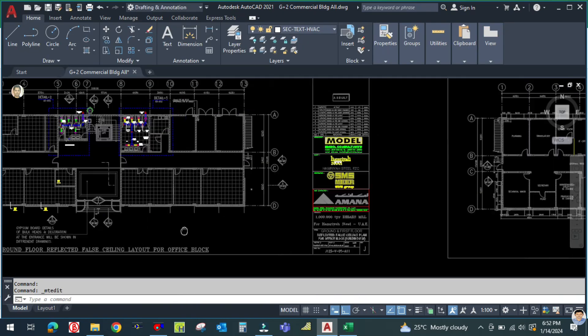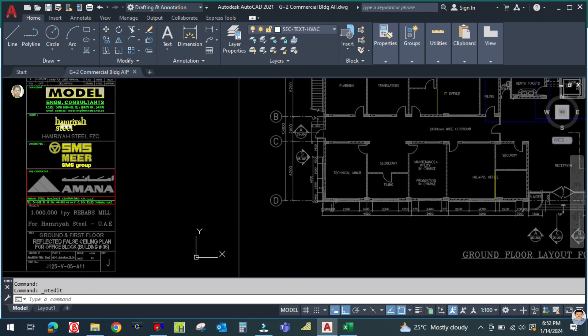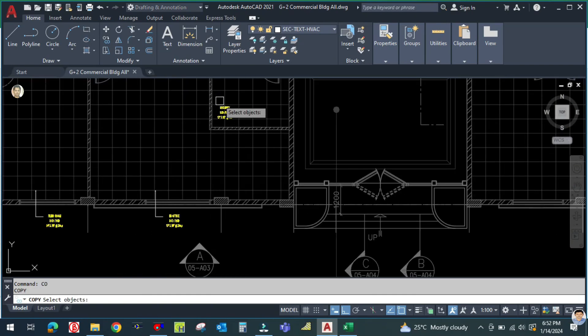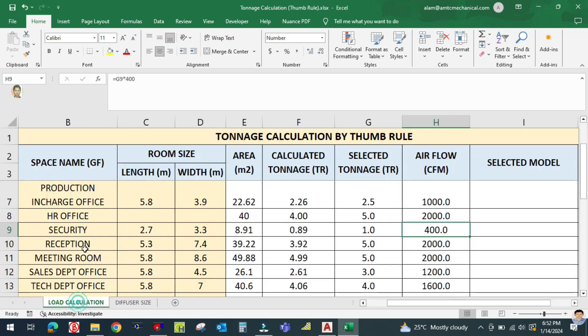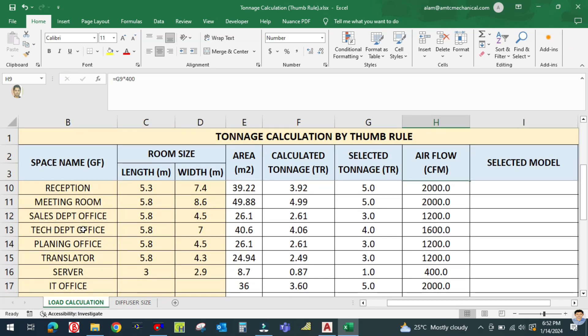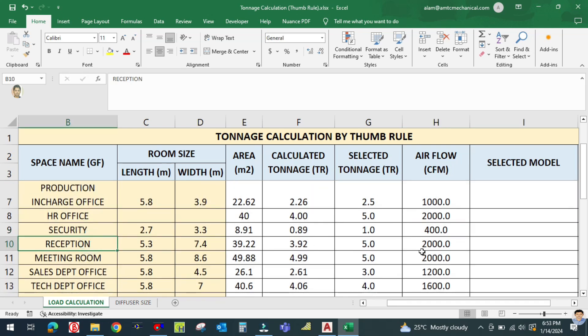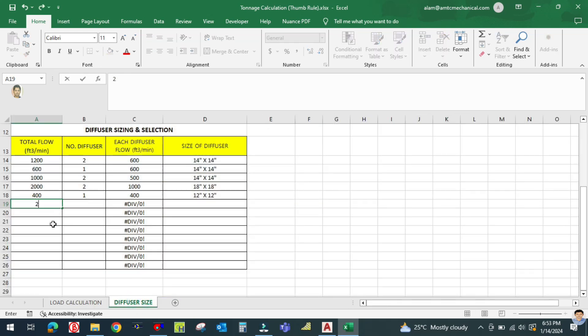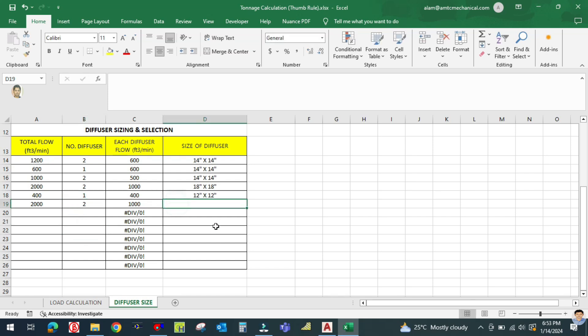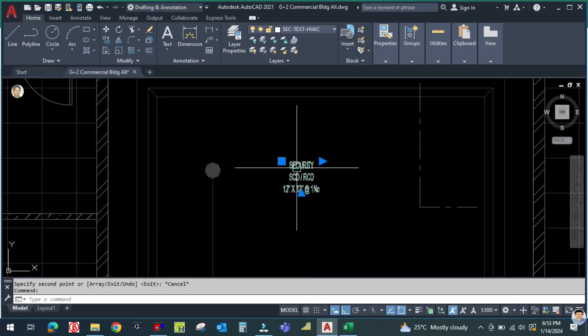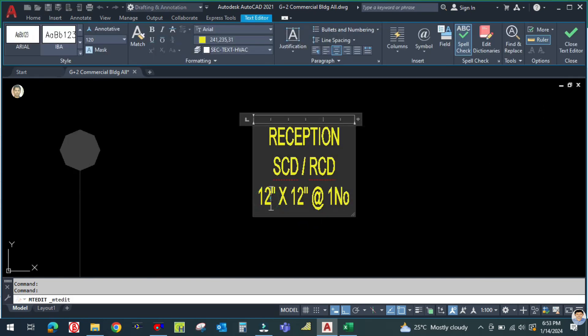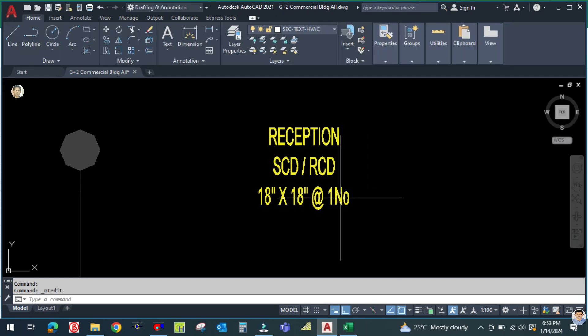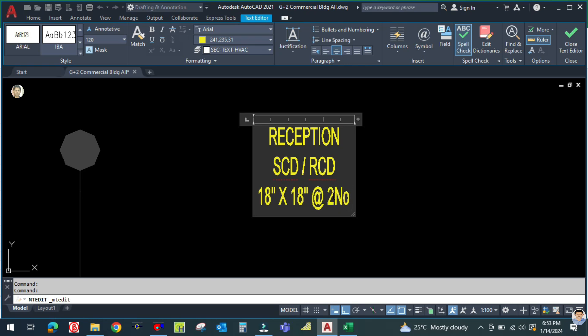For the reception area, copy the text and place it here. The airflow for reception is 2000 CFM. I am going to place two diffusers, so each diffuser CFM is 1000 — the size will be 18 inch by 18 inch. Double click to edit: reception, diffuser size 18 inch by 18 inch, two numbers each.